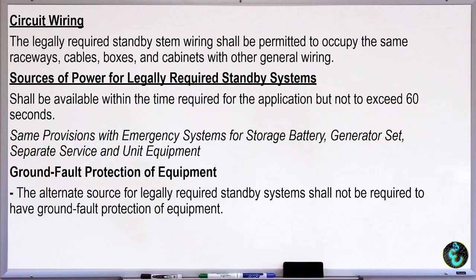So circuit wiring, for this type of system, should be permitted to occupy the same raceway, cable, box and cabinets of the normal wiring or the general wiring. Sources of power for legally required system shall be available within the time required for the application but not to exceed 60 seconds. So it will not go beyond 60 seconds. Same provision for the emergency system for storage battery, genset, separate service and unit equipment. The alternate source for legally required standby system shall not be required to have its own GFCI protection. So same as our emergency system.